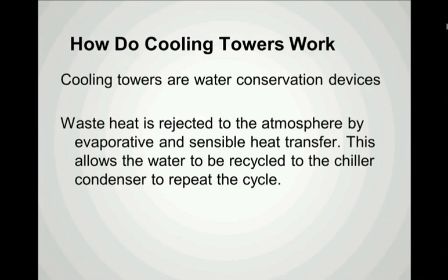So we've talked a bit about cooling towers and how they work to conserve water. They certainly are designed as water conservation devices, and they achieve this by rejecting waste heat to the atmosphere by both evaporative and sensible heat transfer. In doing so, this allows the water to be recycled back to the chiller condenser for reuse prior to discharge to drain.